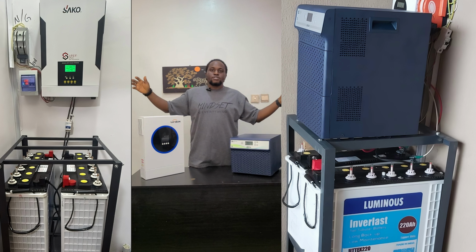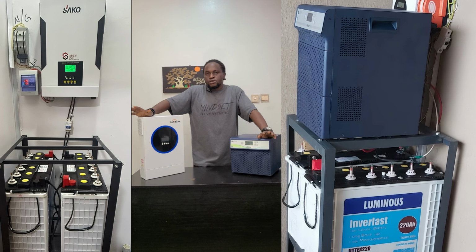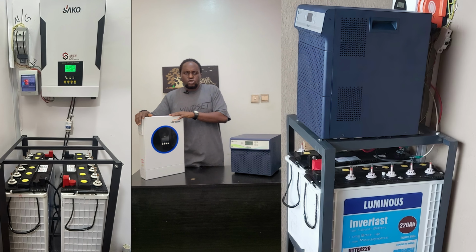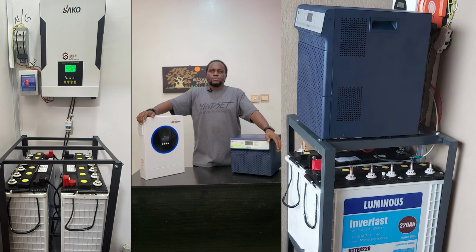And when the sun is at 100% capacity and it exceeds the load in the home, it will take 100% from the sun, and it will even start charging the battery with the balance. It all depends on the user setting. So you can set it that instead of taking the balance from the grid, it takes the balance from the battery, and later in the day when the sun comes up, it will charge up the battery. So that is what made the hybrid inverter to be developed.